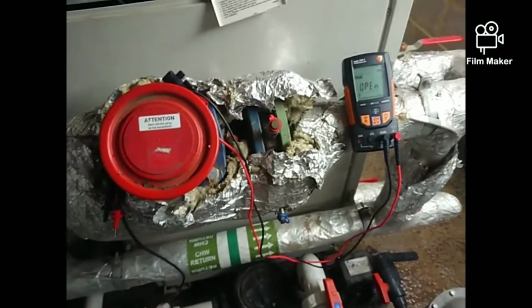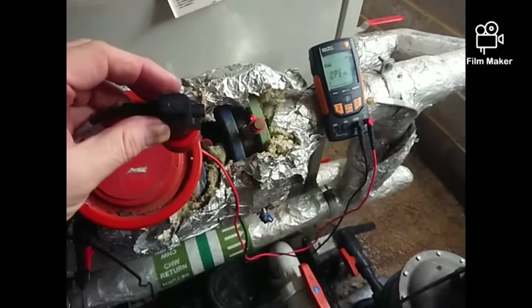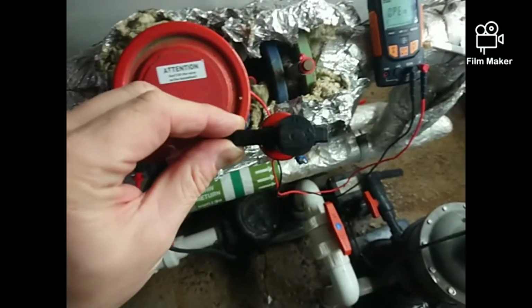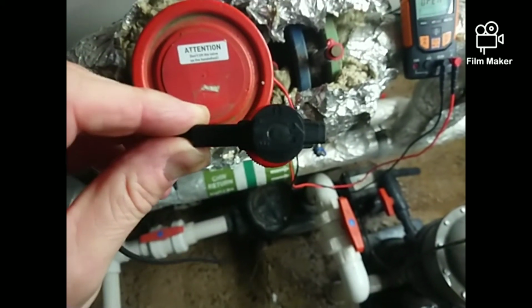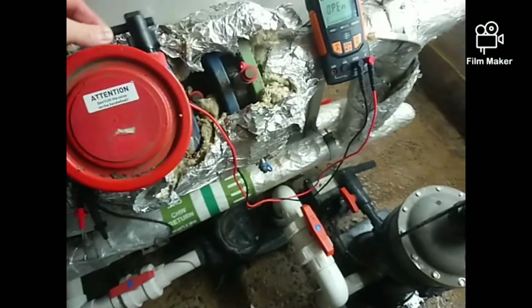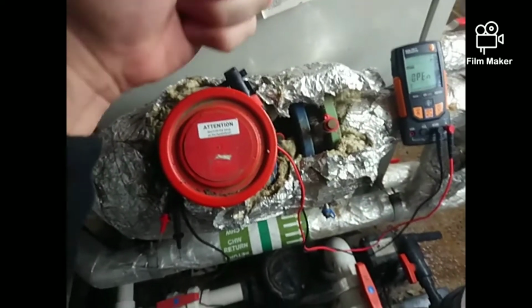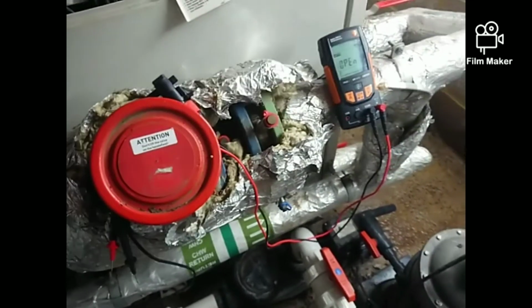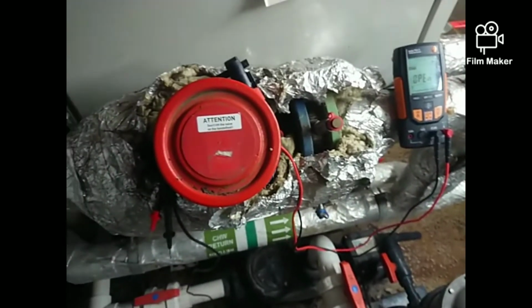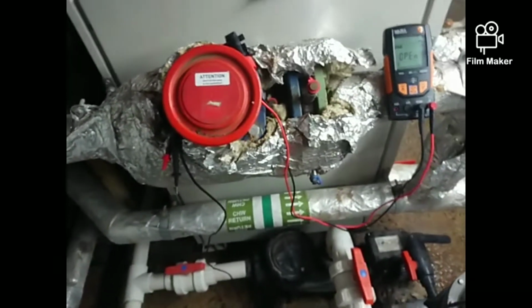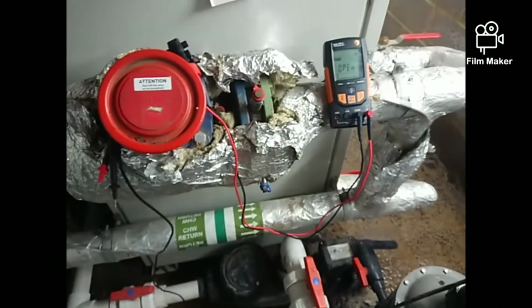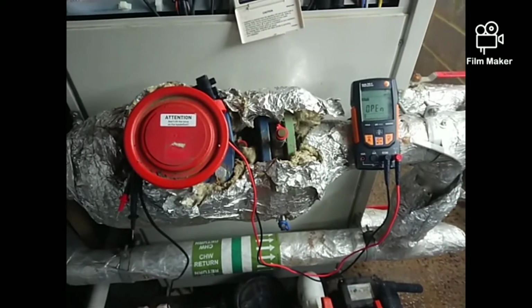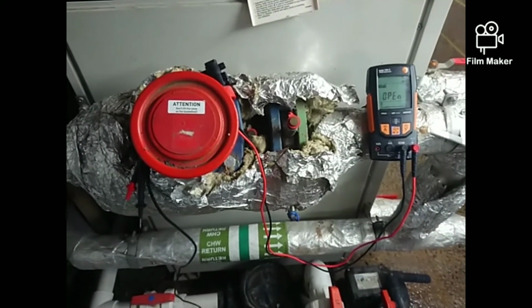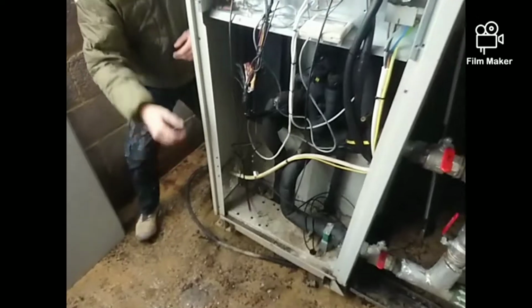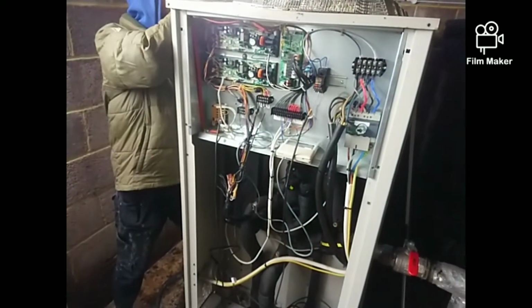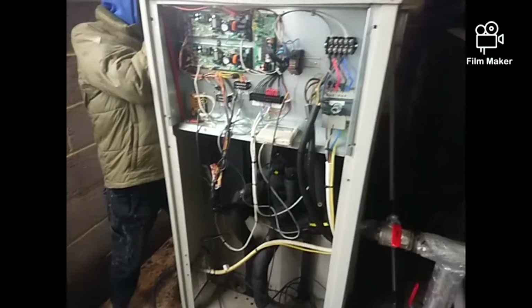straightforward continuity test. And when you put the new one back in, you need to make sure the arrow is pointing in the correct direction, which is the flow of the water. So the flow is pointing in the same direction, so that when the water flows through it, the paddle goes in the right direction. And I think that's about it. It's just putting it back together now, and then we'll run it up.